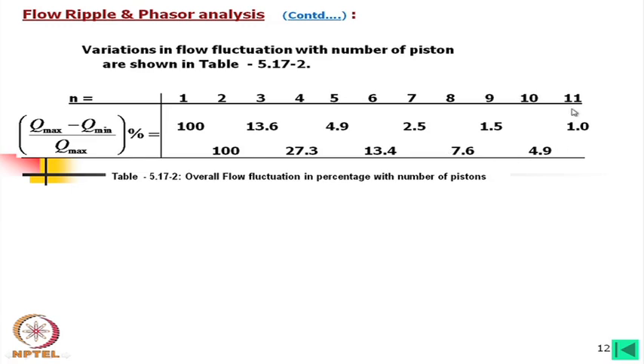For eleven pistons, fluctuation is about 1%, and for thirteen pistons it is less than 0.5% — effectively negligible. This means thirteen pistons would give virtually no fluctuation, making it theoretically ideal for smooth flow, though the cost increases significantly with more pistons.